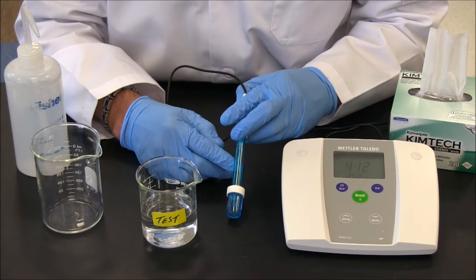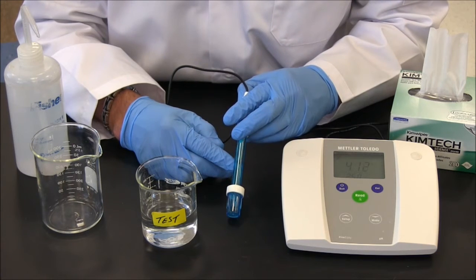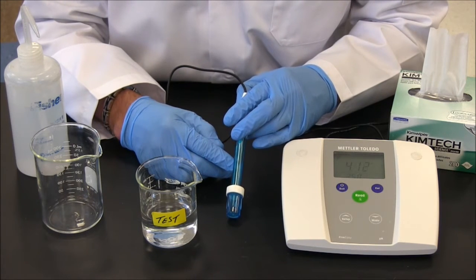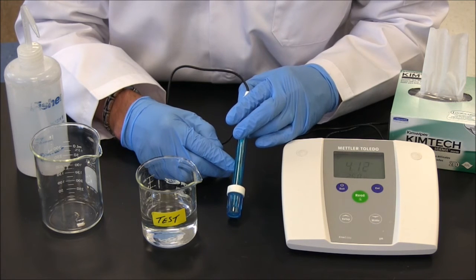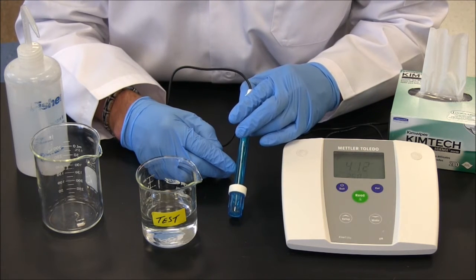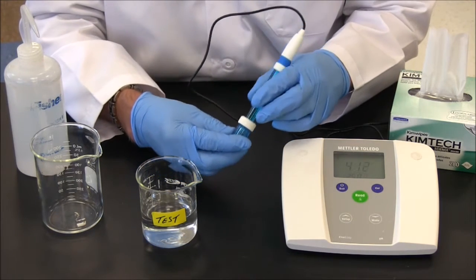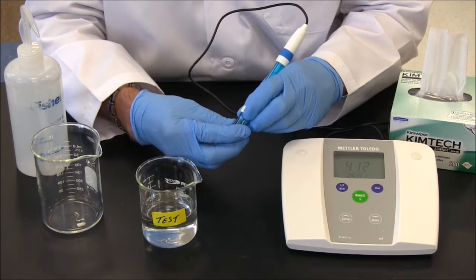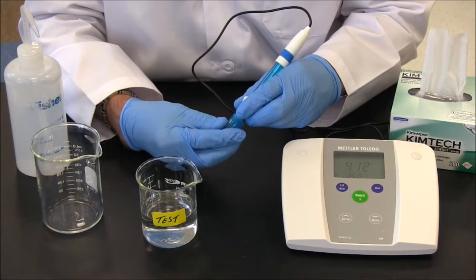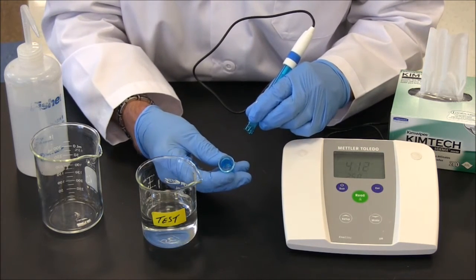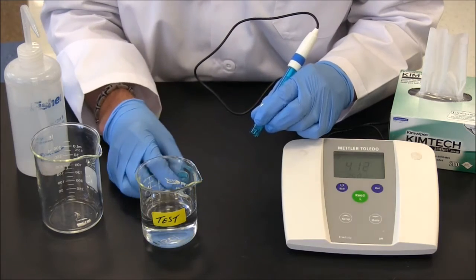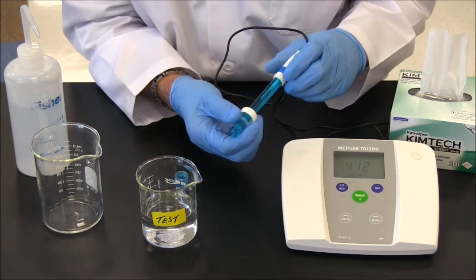Before you begin to use your pH probe, you have to make sure that it's calibrated against your meter. This is usually done using 3 different pH buffer solutions, 4, 7, and 10. Just follow the manufacturer guidelines for your meter. When you're ready to take a measurement, you want to remove the protective cap at the bottom of your probe. It contains a storage solution that keeps the membrane from drying out.